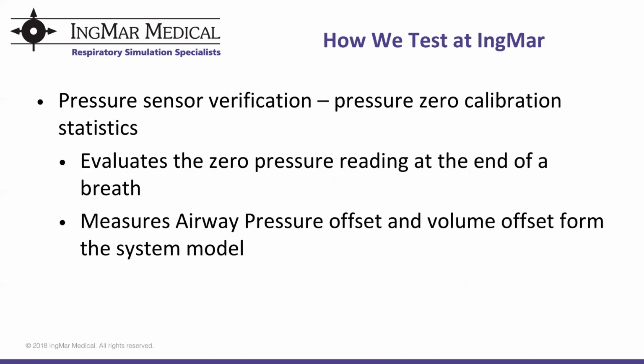The next test we call pressure sensor verification, pressure zero calibration statistics. This test verifies that the analog noise in the sensor is minimized when the system is breathing. We want to assure zero pressure is maintained and constant at the end of each breath.